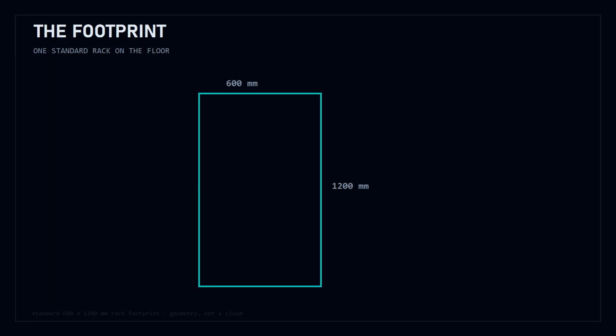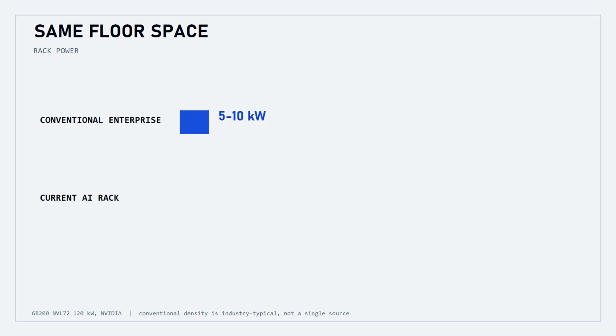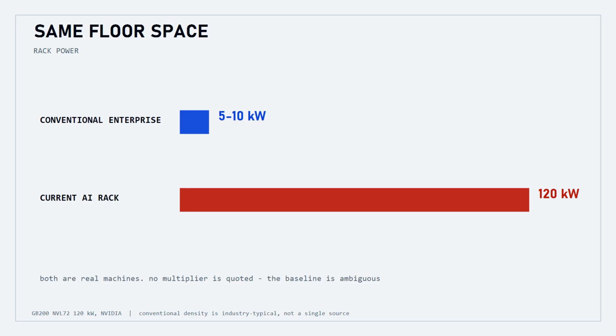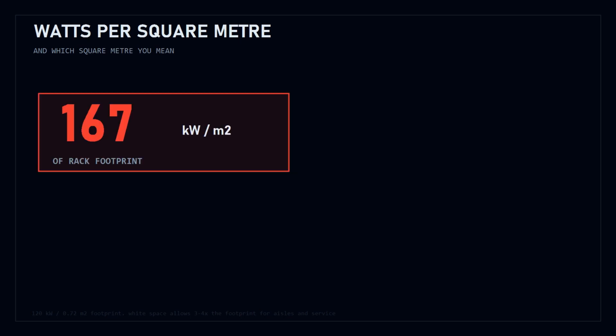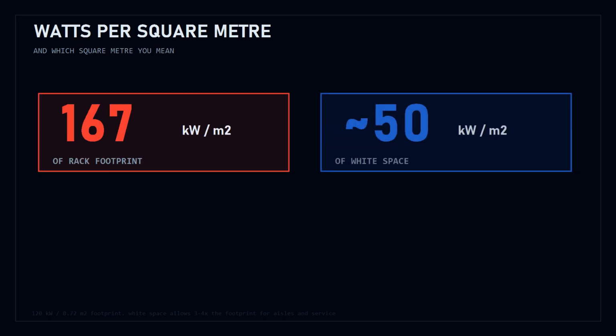A standard rack occupies 600 by 1200 millimeters, 0.72 of a square meter of floor. A conventional enterprise rack in that footprint draws 5 to 10 kilowatts. A current AI rack draws 120. Divide it out, 167 kilowatts per square meter of rack footprint. Spread across the aisles and service space a real hall needs, it is nearer 50. Both numbers get quoted, and only one of them is a floor plan.